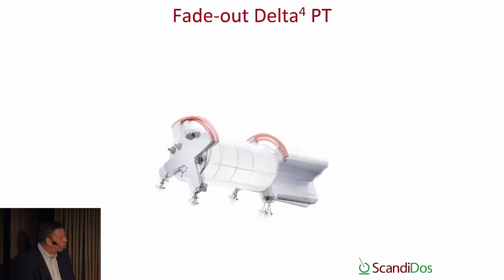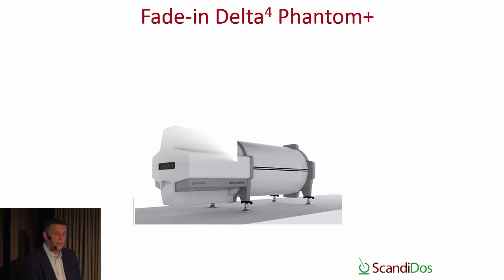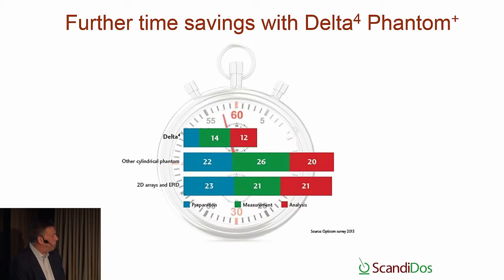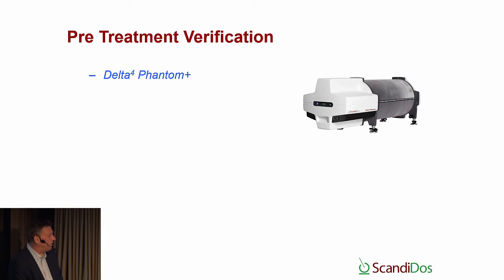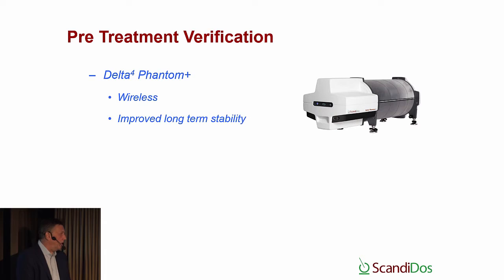So what we decided was to fade out the Delta4 PT and fade in the Delta4 Phantom Plus. It's a completely new design, but built on the same concept as the Delta4 PT. Now you can see that the blue part is very, very short, and it's nearly instant to set up the system. It's just to align it and then go. So it's very quick. And the reason is that the Delta4 Phantom Plus is wireless. It's wireless in the way that it works with Wi-Fi, so it's wireless communication of data, but it also runs on battery. So you don't have to hook up any cables to the system.